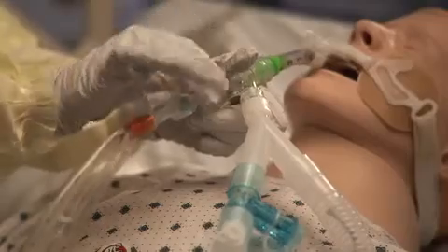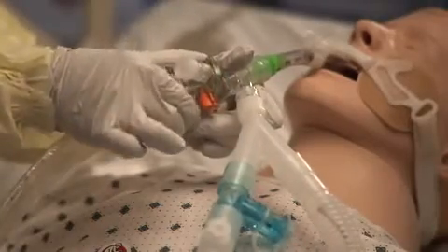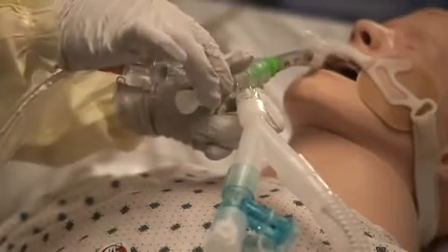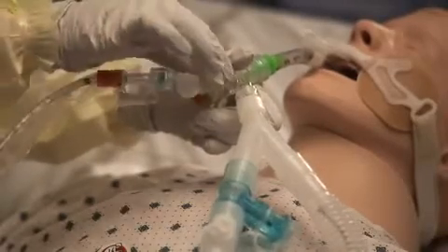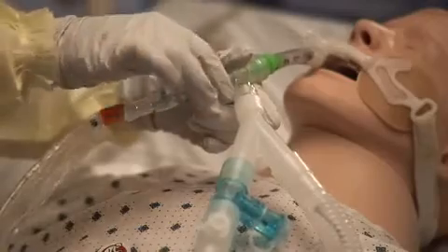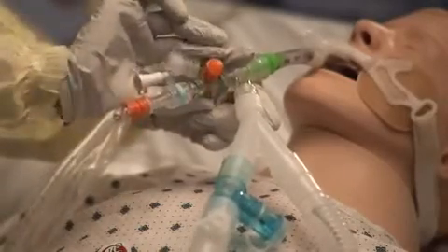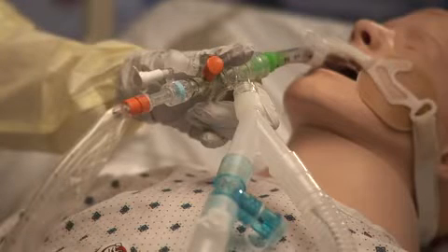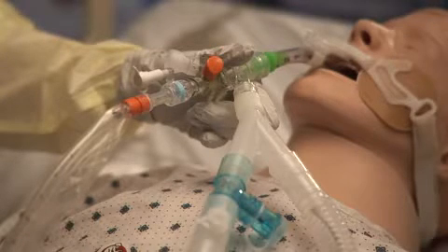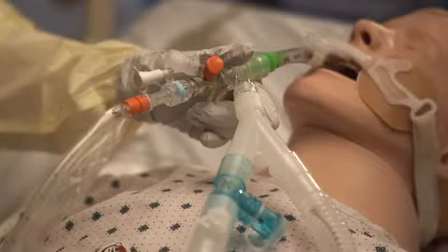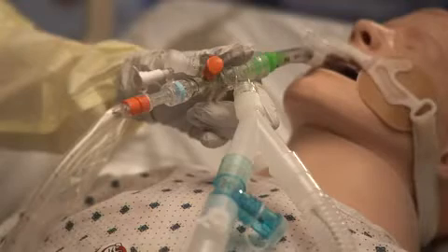But with Kimvent multi-access port closed suction system, the compact rotating manifold provides multiple ports to access the patient's airway, locking into place with a click. This reassures that the circuit remains sealed, enabling catheter replacement without opening the circuit. The single-use seal cassette maintains PEEP during insertion of a sampling catheter or other devices, so both suctioning and alternate procedures can be performed while maintaining a closed vent circuit.